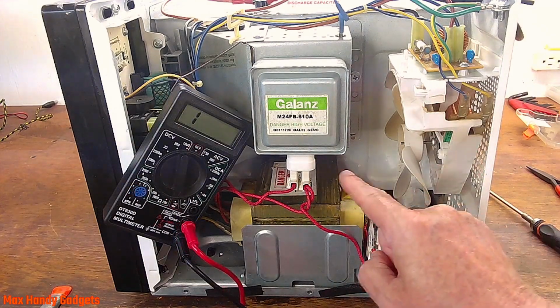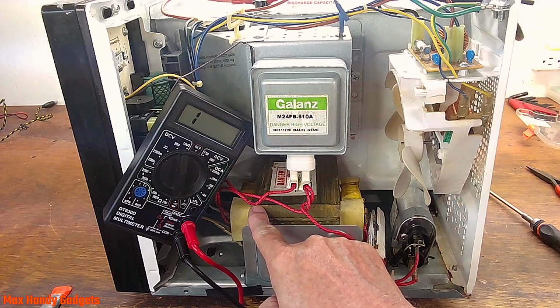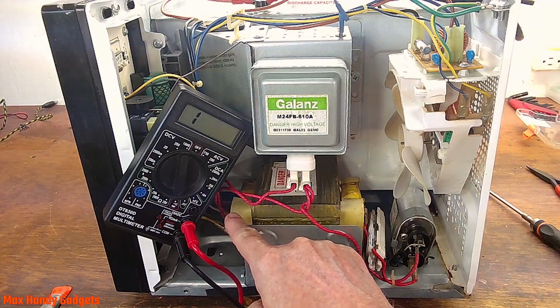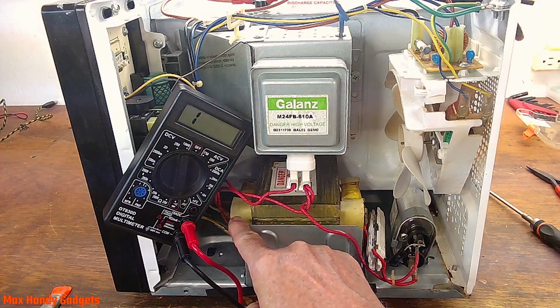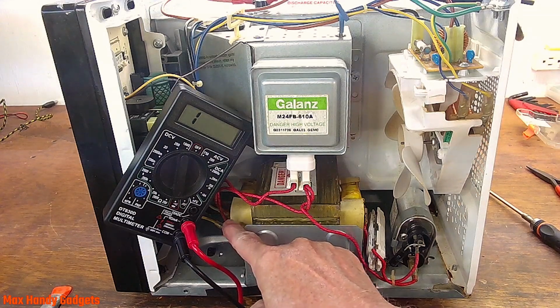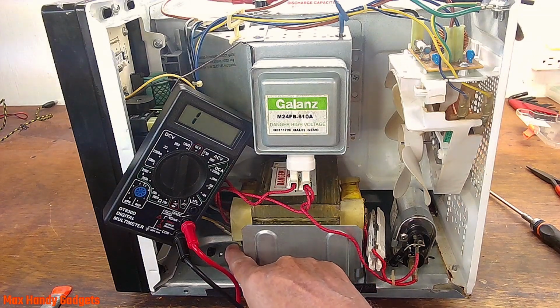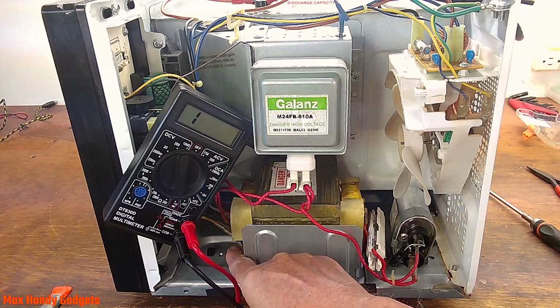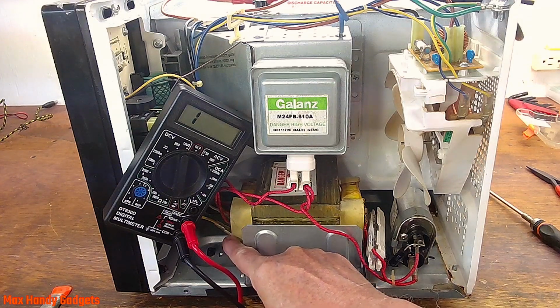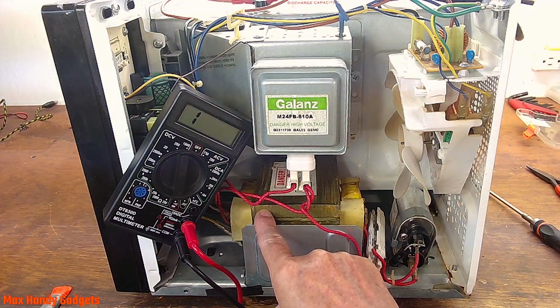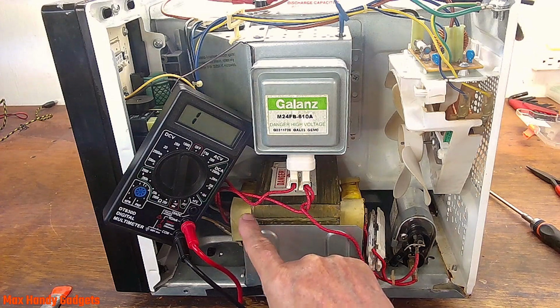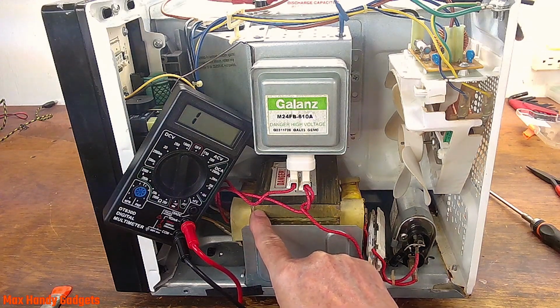In part 1, we found out the transformer primary windings were shorted out somewhere, maybe right near the end of the terminal there. We just don't know. I detected some black windings right down at the bottom there. So we're going to have to take this transformer out, turn it over, and see what's going on. Maybe we can fix it.